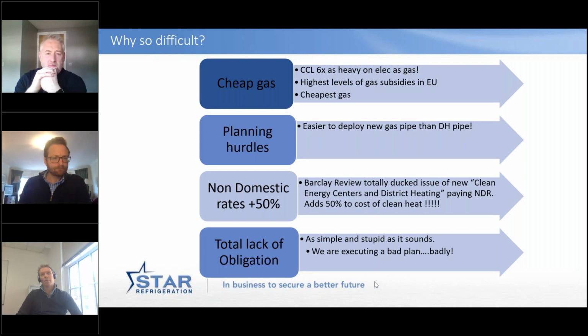You can then dynamically vary the flow temperature into those radiators according to various factors, and that gives you thermal flexibility in the amount of thermal power delivery going into the property according to real-time demand. A lot of the time those radiators can be running at 60, 65 degrees. You may still need some redundancy, some kind of bivalent system with a bit of higher temperature in it, or a heat pump designed to go up to a higher temperature.